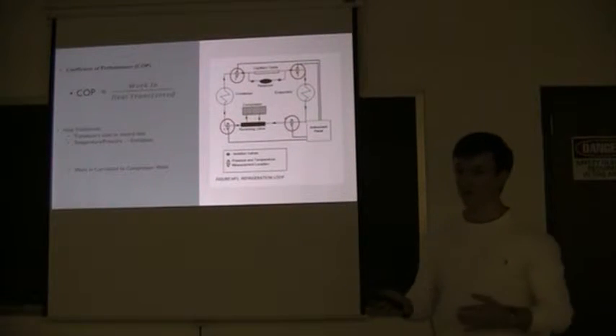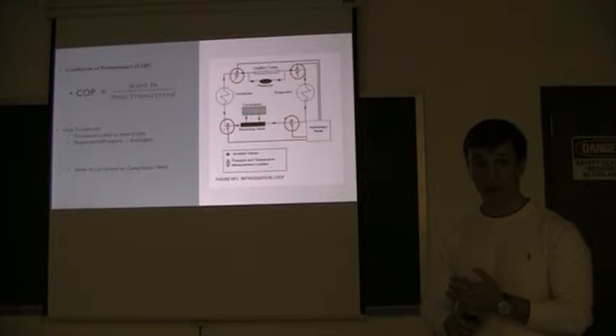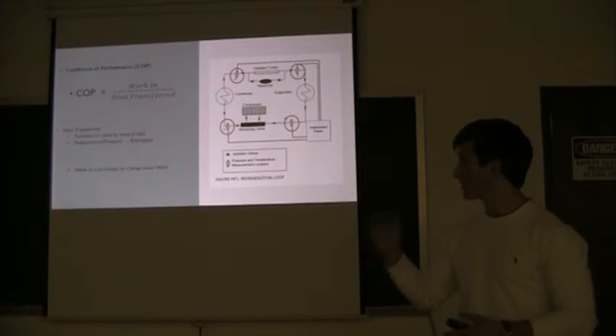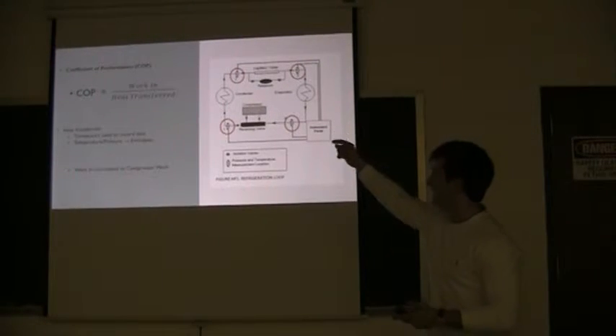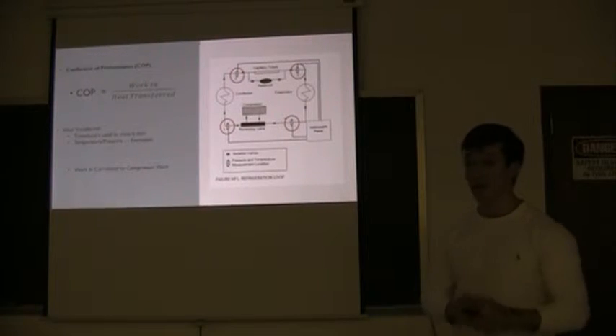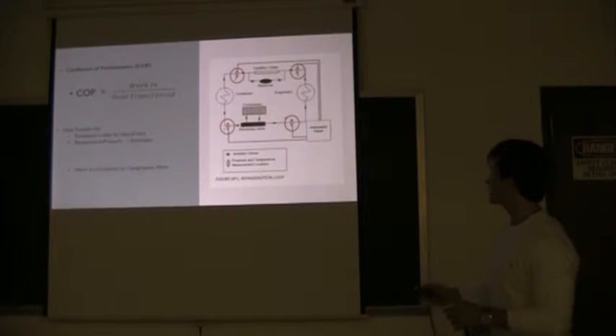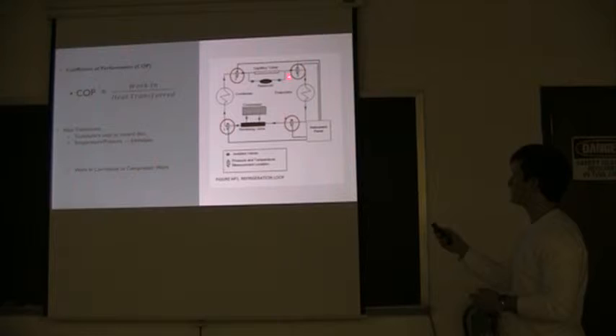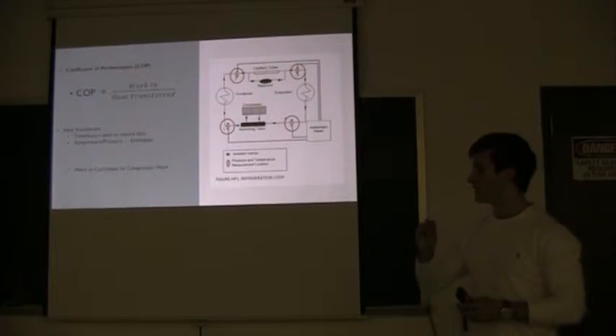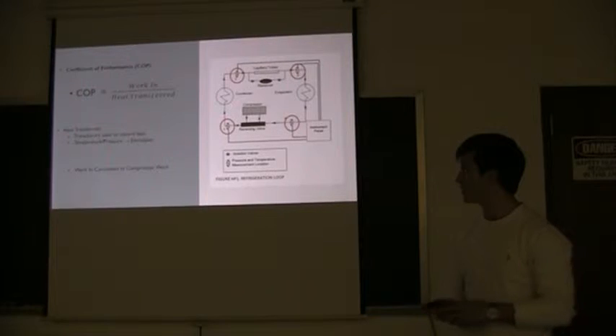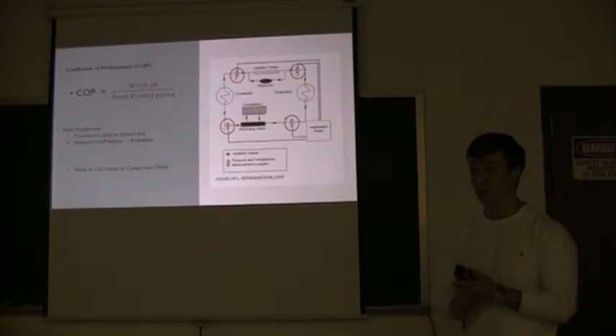So a coefficient of performance, what you care about is how much heat you're able to transfer over the work in. It's actually upside down here. But the way that we're going to measure that, we have pressure transducers. You can see the red circles here, here, here, and here, at the inlets and outlets of all of the equipment. And we're going to take that temperature and pressure and correlate it to the enthalpies.